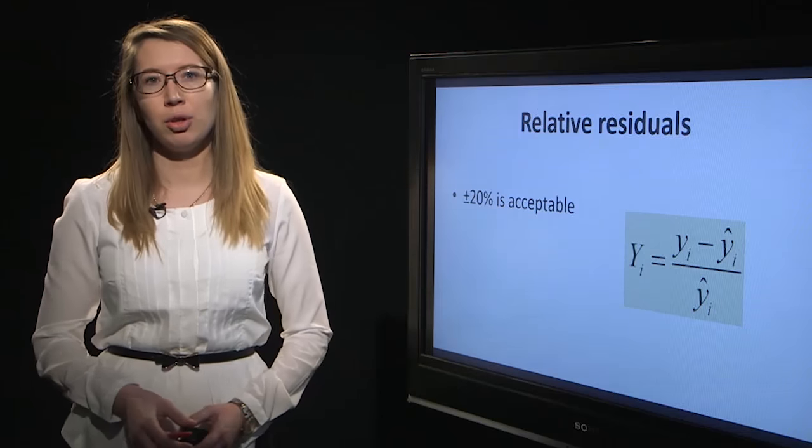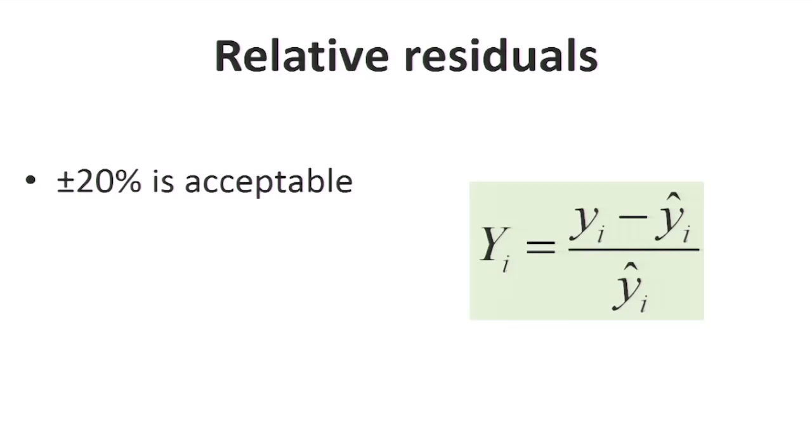In addition to the plot of residuals, SANCO guidelines also suggest using relative residuals, which we obtain when we divide the residuals with the calculated signal value. And the relative residuals should be within ±20% for the calibration model to be acceptable.